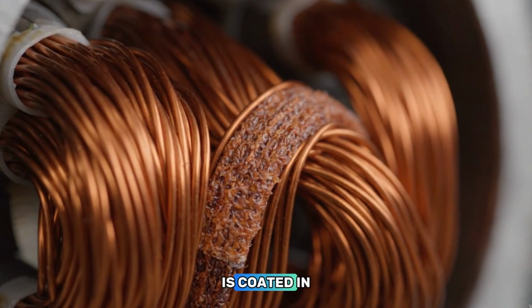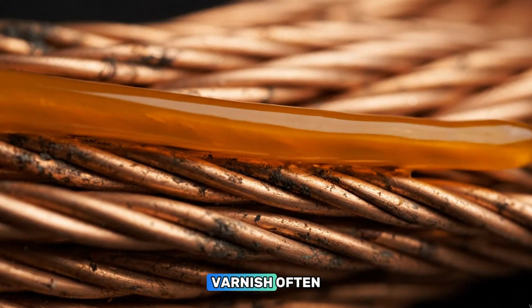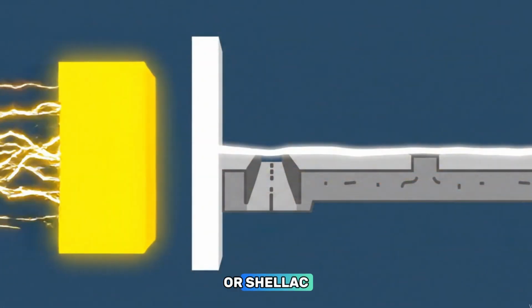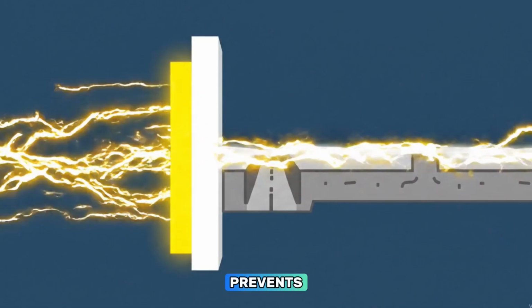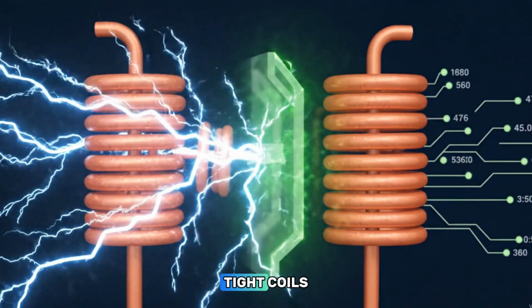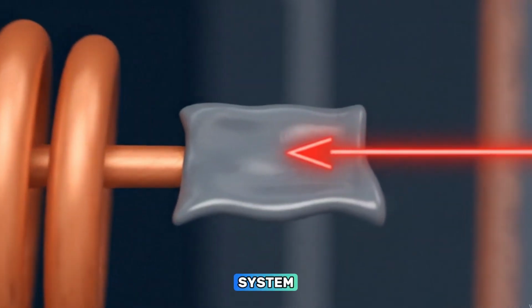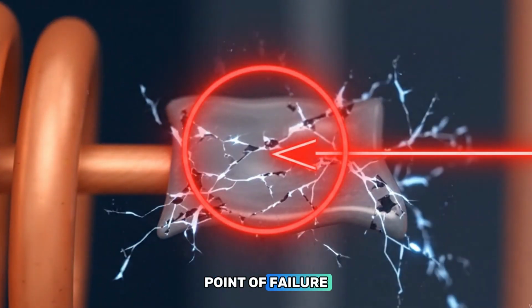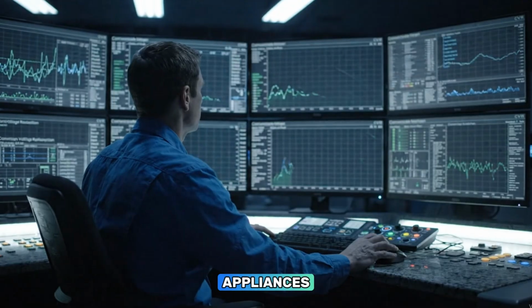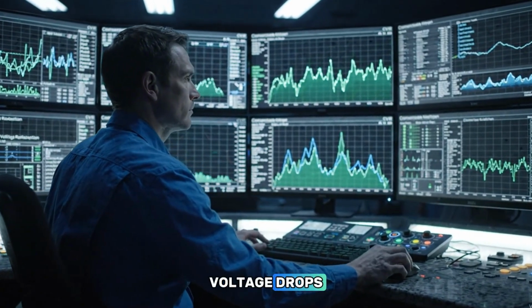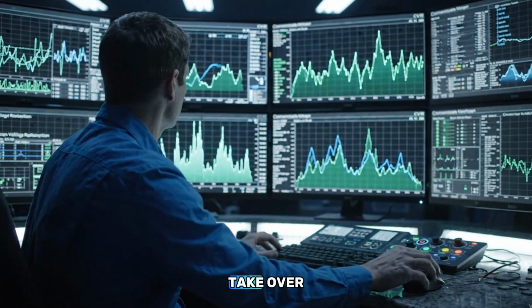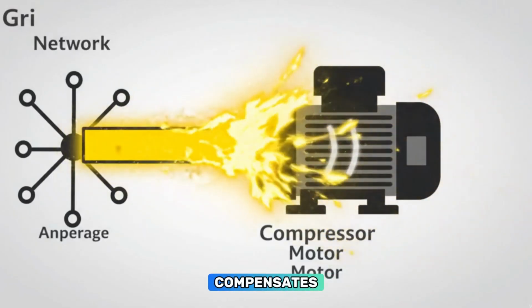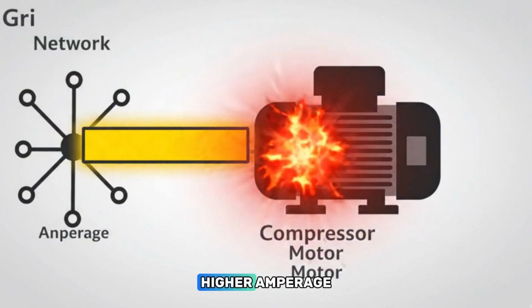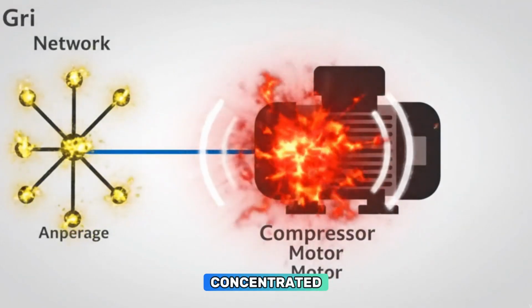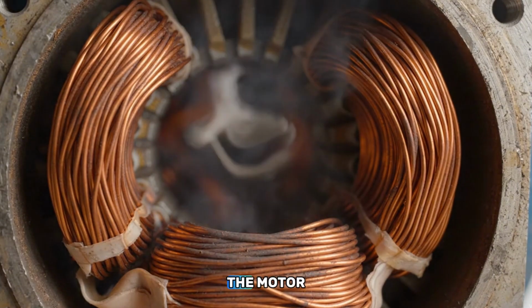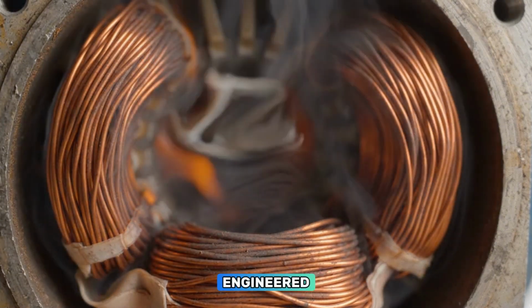Every individual strand is coated in a microscopic layer of insulating varnish, often a synthetic polymer or shellac. This ultra-thin coating prevents the massive electrical current from arcing between the tight coils and short-circuiting the entire system. This varnish is the single point of failure. It is the Achilles heel of modern appliances. When the grid voltage drops and conservation voltage reduction algorithms take over, your compressor motor compensates by drawing higher amperage. Higher amperage creates intense, concentrated heat deep within the copper coils. The motor is operating far outside its engineered thermal envelope.